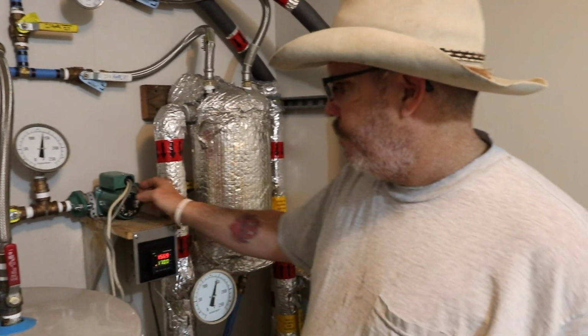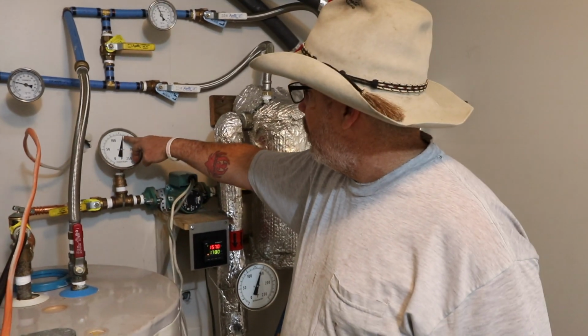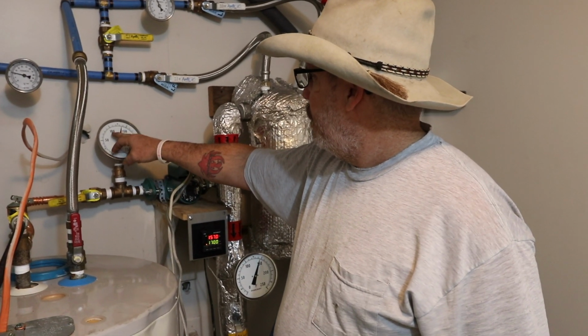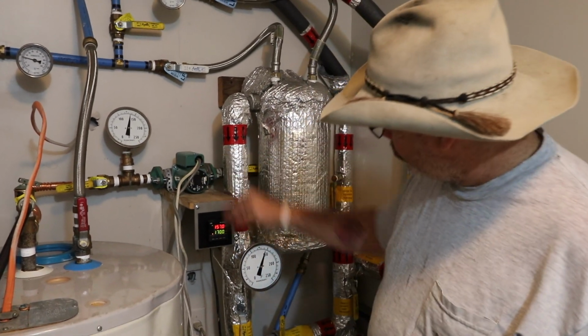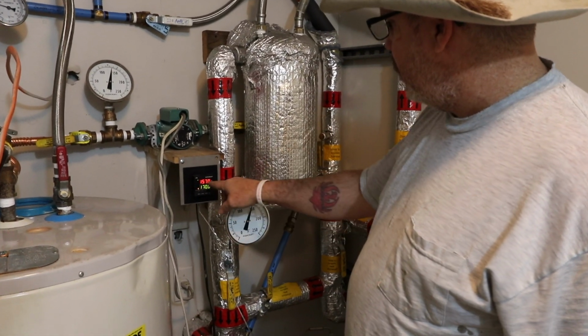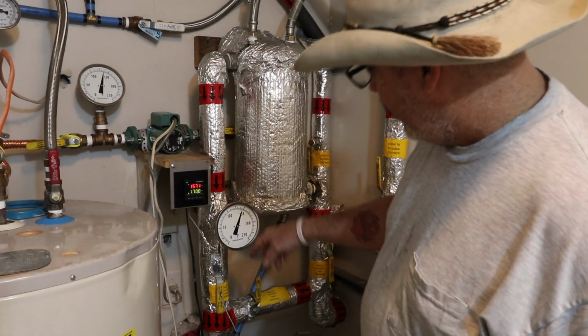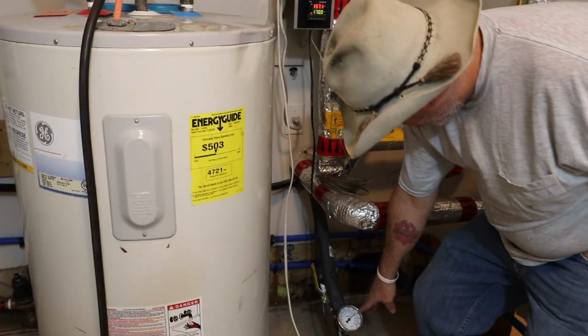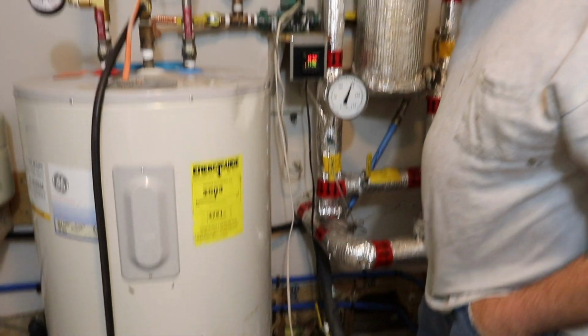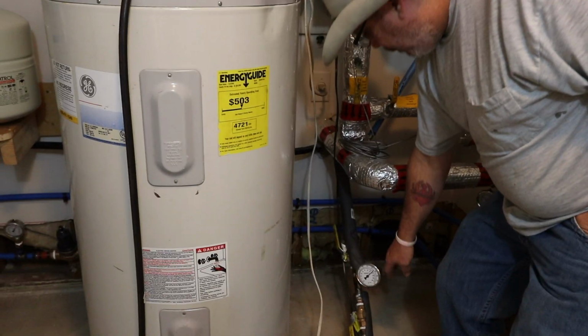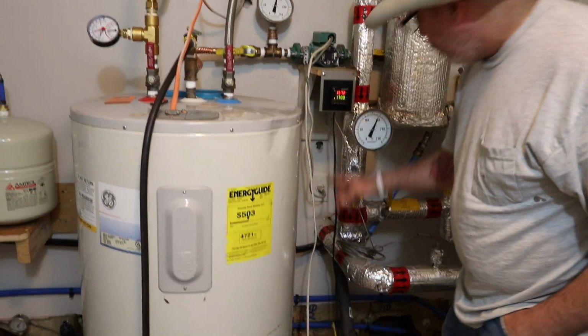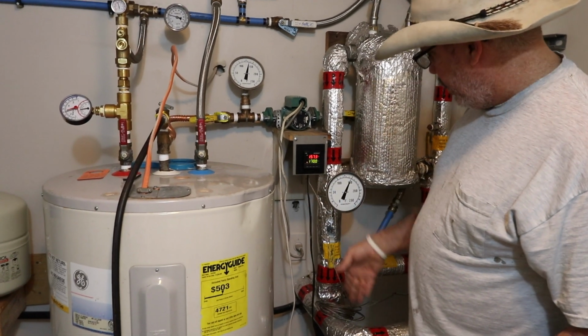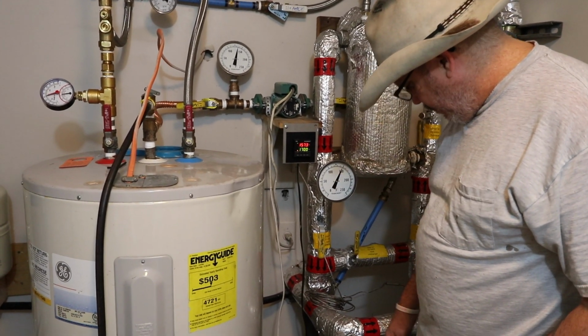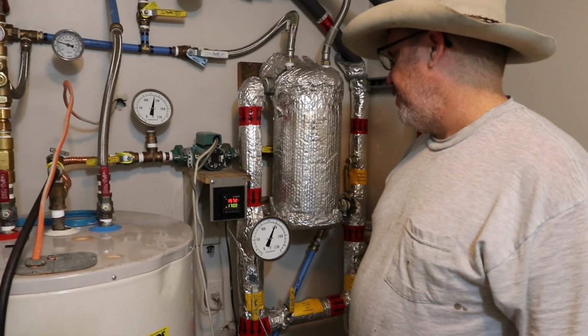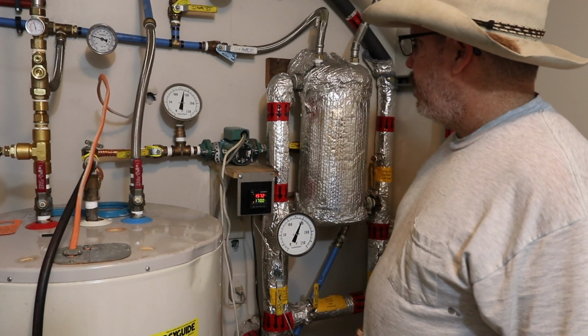Okay, so say for instance we're putting about 135 degree water into here. My boiler temperature water coming over here is 157. The boiler should be running right now, because we're putting a big demand on it so far this morning. But I've got 150 degree water coming back. So basically that boiler water and my domestic water in that coil inside the boiler is pretty close, about 153, 157. I don't have a lot of heat loss.